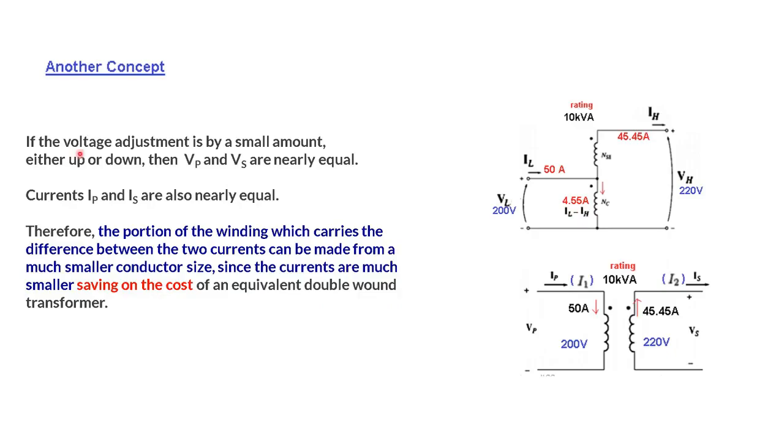Here the voltage adjustment is by small amount either up or down. VP and VS are nearly equal. The currents IP and IS are also nearly equal. Therefore the portion of the winding which carries the difference between the two currents can be made from a much smaller conductor size. Since the currents are much smaller saving on the cost of an equivalent double wound transformer.